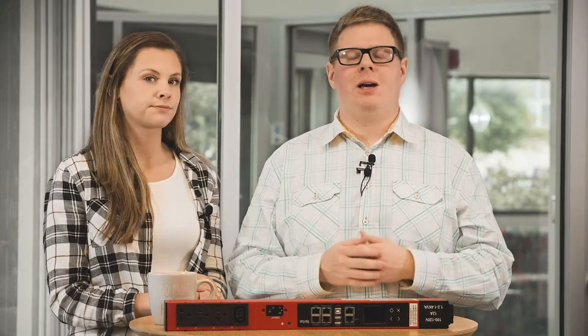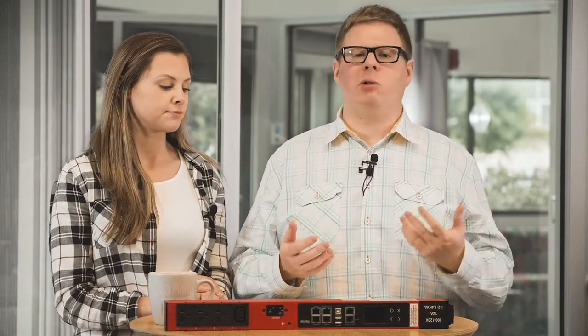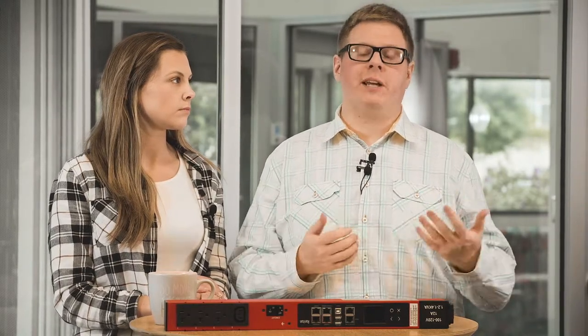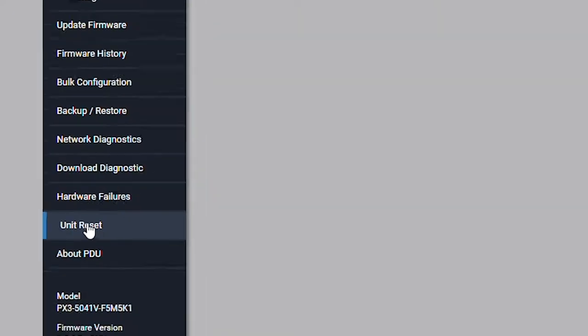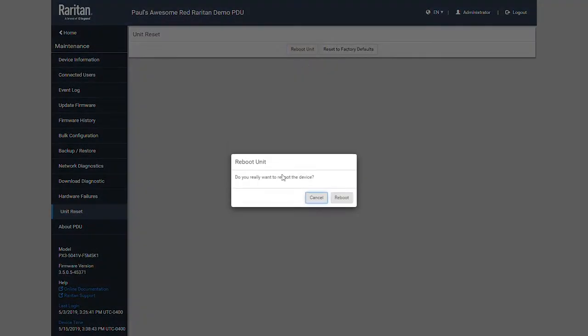A PDU controller can also be reset remotely. A data center operator doesn't always have a local resource to physically go to a PDU and hit a reset button. That's what makes web GUI and command line interface extremely valuable tools for resetting a PDU. To remotely reset a controller through a web GUI, a user can browse to the maintenance menu to quickly perform this action without ever needing to access the PDU hardware itself.